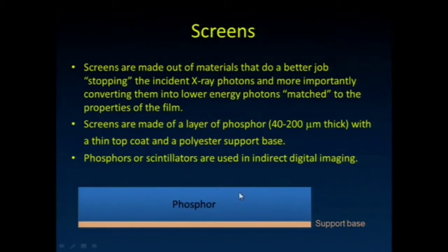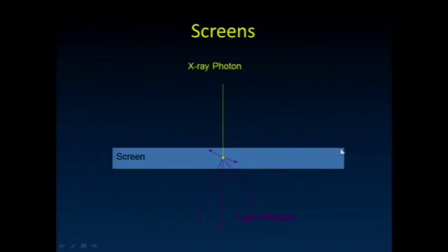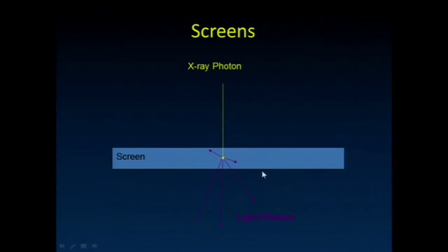Screens do a better job stopping those X-ray photons, usually made out of a material that has a higher Z than the material that makes up our detector — either the film or our detector elements on a digital detector. Phosphors and scintillators are analogous to screens used in indirect digital imaging. The X-ray photon strikes this screen material and converts this X-ray energy into multiple lower energy light photons. These are much more easily stopped and detected by a CCD camera or by film. The downside is they disperse out a little bit and therefore cause some blurring in the image.